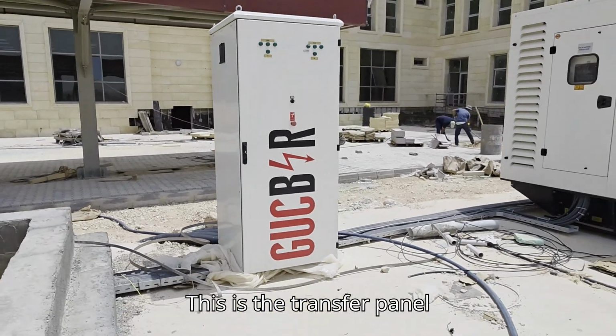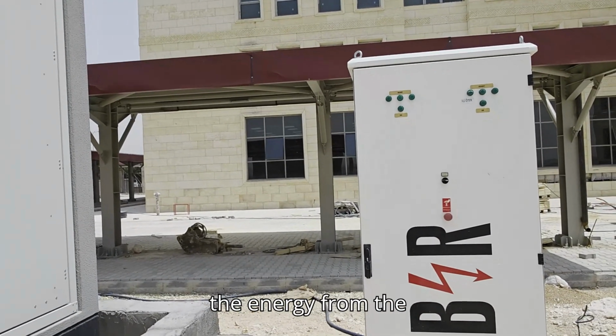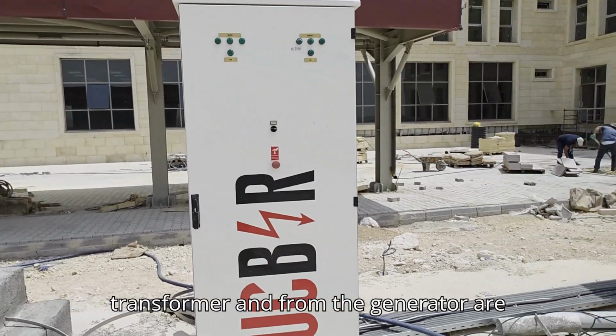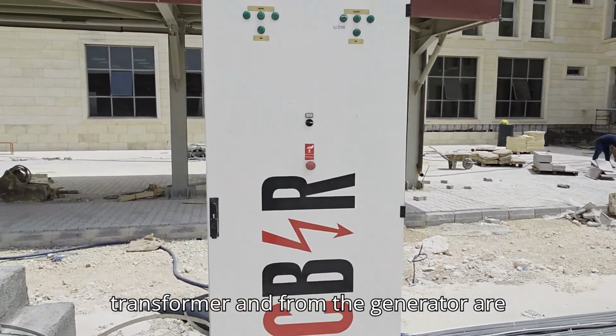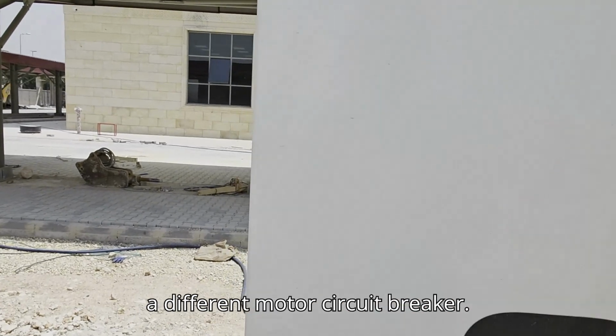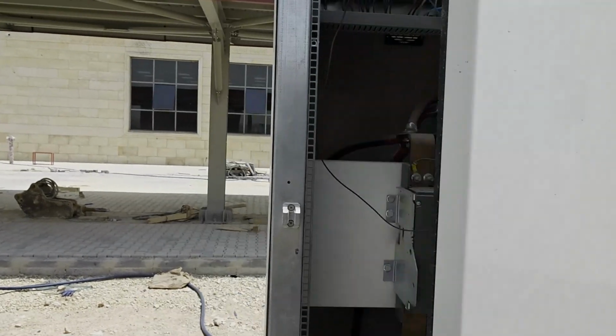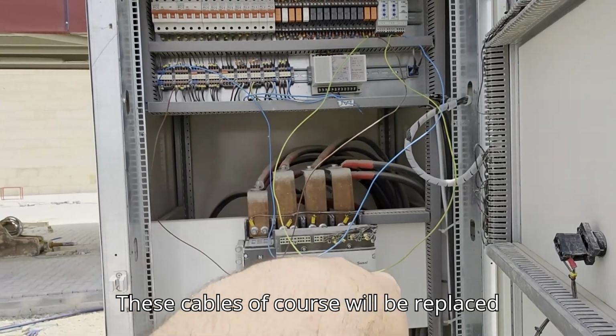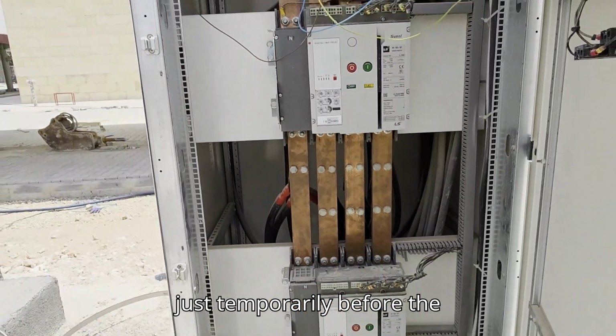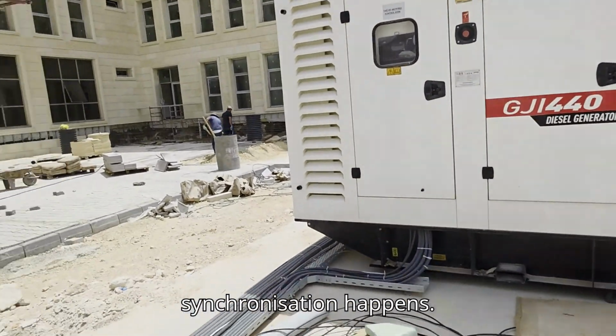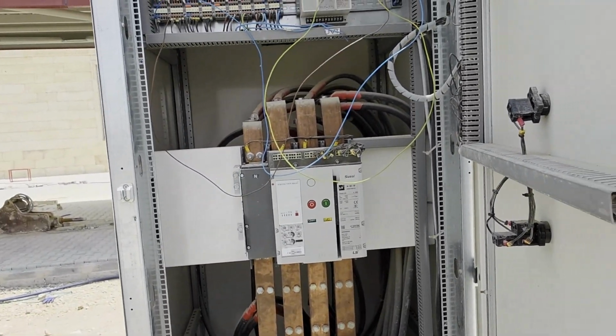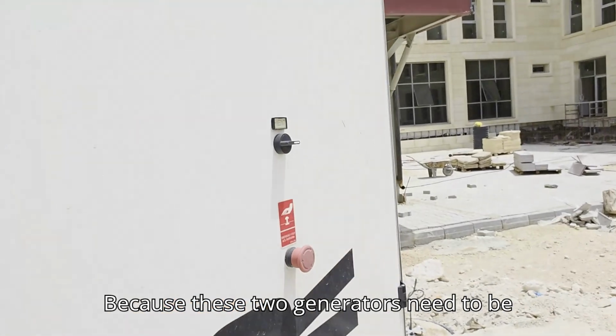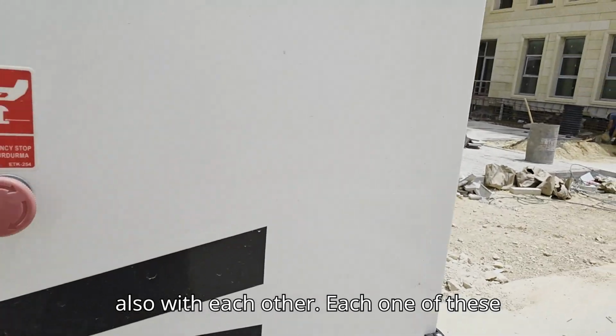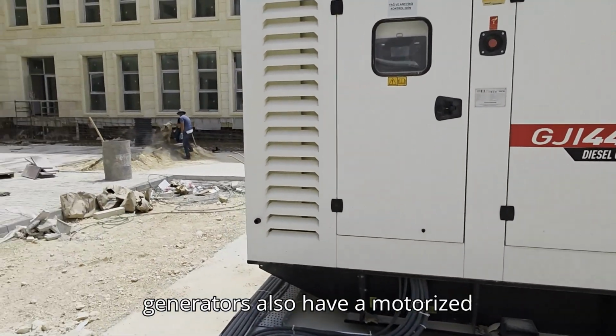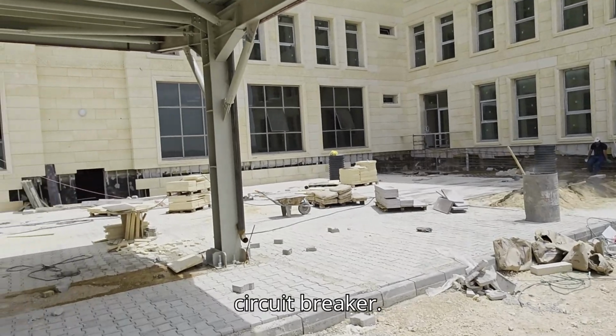This is the transfer panel, automatic transfer panel, where basically the energy from the transformer and from the generator are combined. Of course, each one of them has a different motor circuit breaker. These cables, of course, will be replaced just temporarily before the synchronization happens, because these two generators need to be synchronized with the grid and also with each other. Each one of these generators also has a motorized circuit breaker.